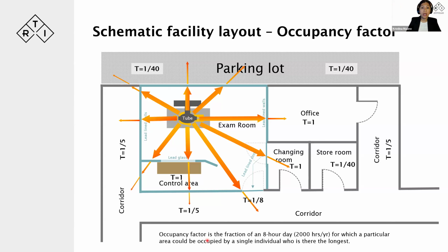Usually the use of the occupancy factor when doing our shielding calculations leads to a normalized dose, and this indicates the amount of time that these areas adjacent to the X-ray room are actually occupied. Normally there are very little changes to this, but as I said, there could be instances over a period of time where some issues arise, and so we do our measurement and testing for stray radiation.